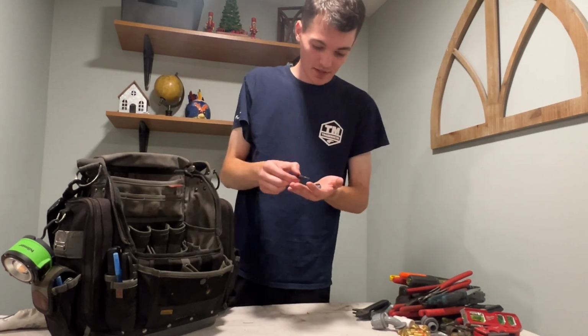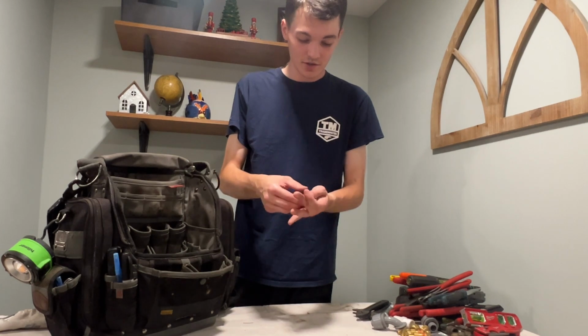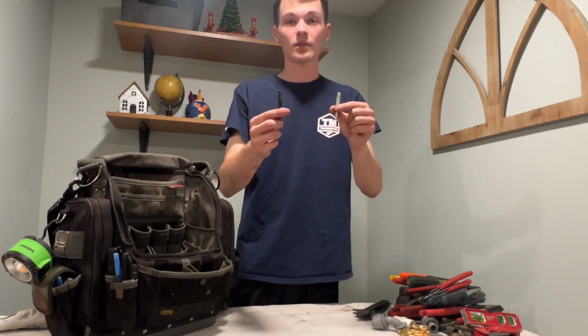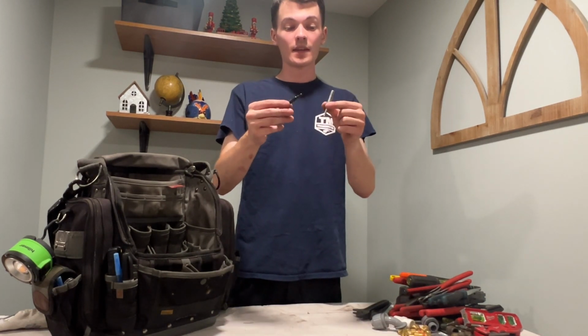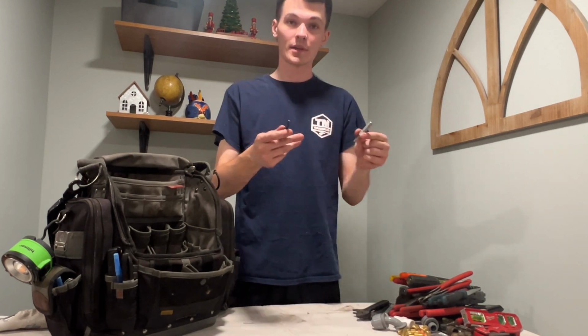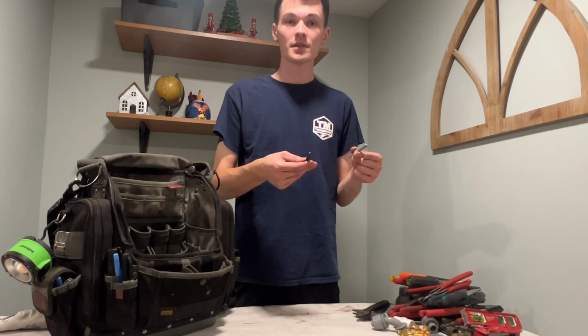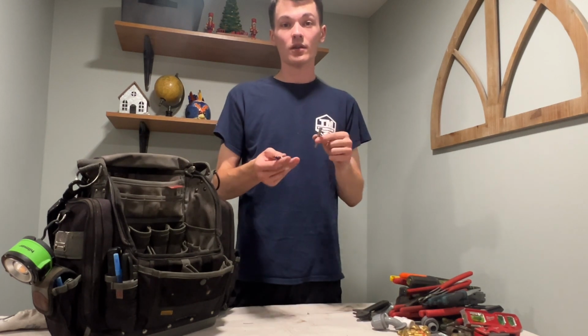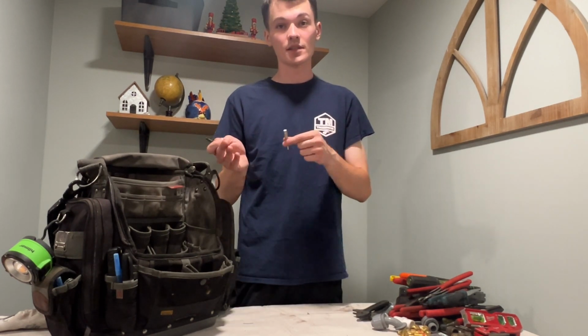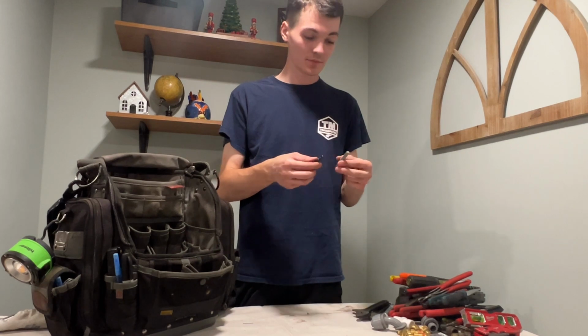Every technician needs to have a service wrench, and what I have here are the Allen sizes that connect to your service wrench to open up your king valves, your service valves, when you're closing or opening off your condensing unit to release the charge into the line set or to pump the charge down.